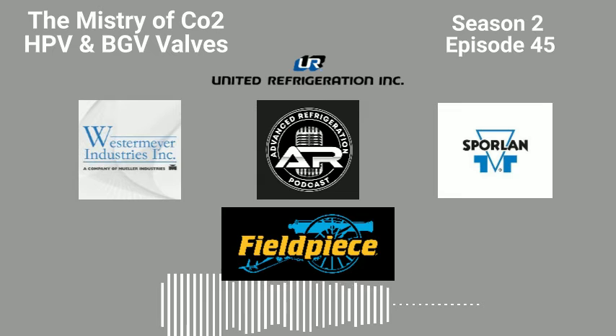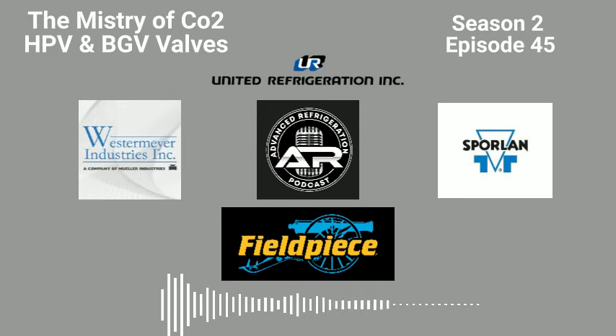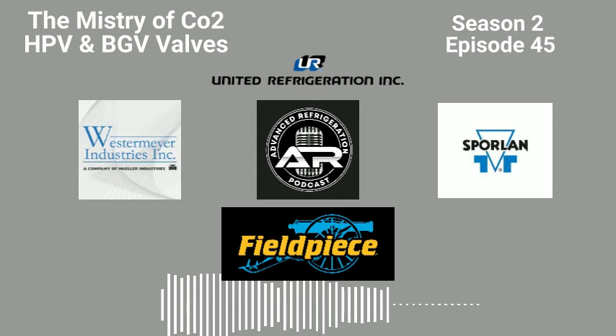So now that we have this high pressure valve, and we have this balancing act going on where we're holding back, and we're trying to maintain that subcooling, at the same time we're trying to maintain that receiver pressure from getting too high, and or the condenser pressure from getting too high. That's all in the parameters. Now we're going to move on to the bypass valve. So what you have now is we need to reduce this tank pressure even more, and we need to do it faster. What we do here is we have what's called a flash gas bypass valve. It can be called a flash gas bypass valve, economizer line bypass valve, FGB valve. So this valve's one and only purpose is to maintain receiver pressure.